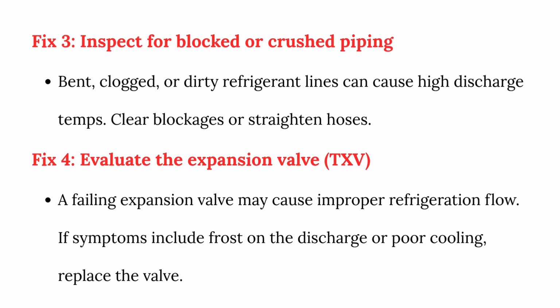Fix 4. Evaluate the expansion valve, TXV, for failure. A failing expansion valve may cause improper refrigerant flow. If symptoms include frost on the discharge or poor cooling, replace the valve.